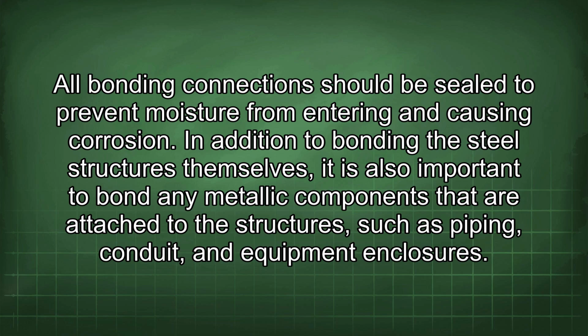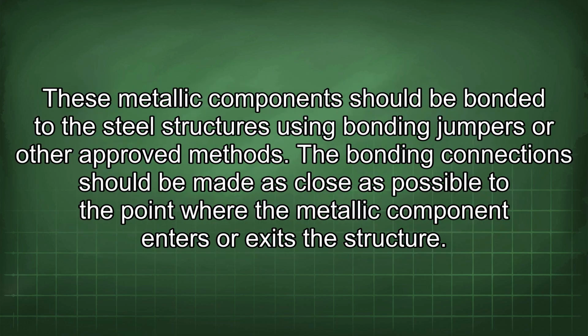In addition to bonding the steel structures themselves, it is also important to bond any metallic components that are attached to the structures, such as piping, conduit, and equipment enclosures. These metallic components should be bonded to the steel structures using bonding jumpers or other approved methods. The bonding connection should be made as close as possible to the point where the metallic component enters or exits the structure.